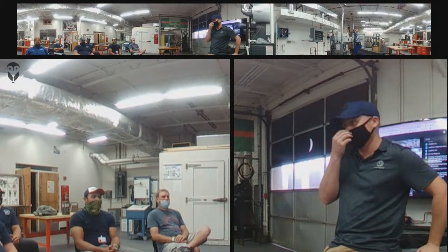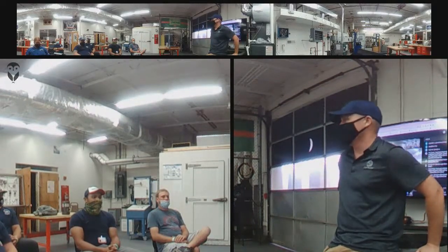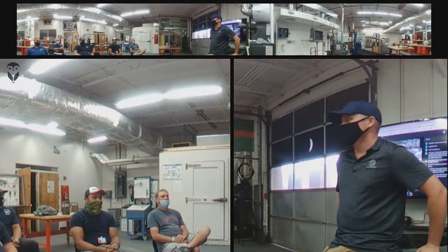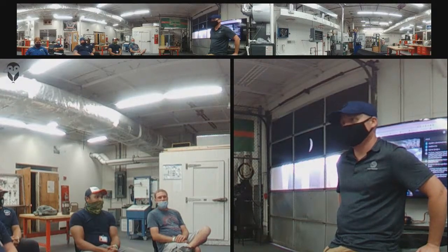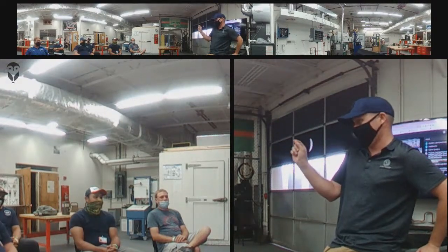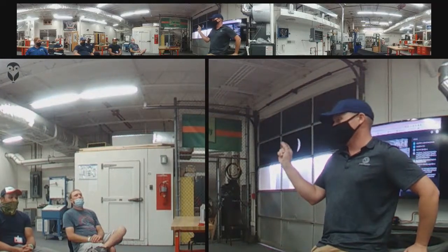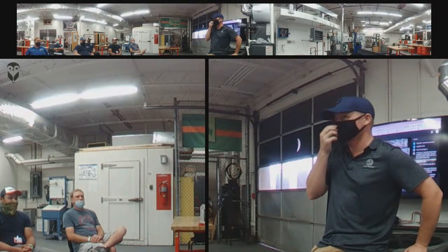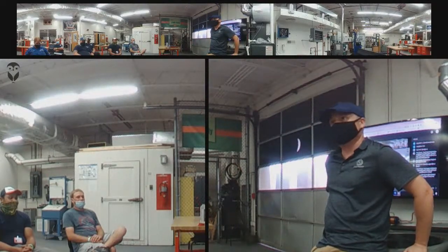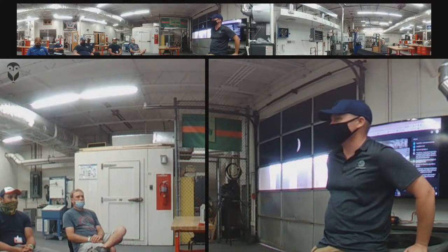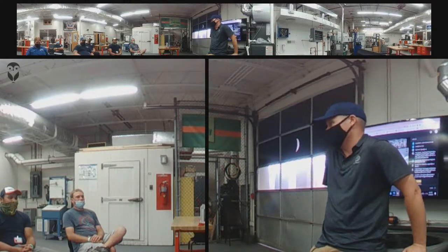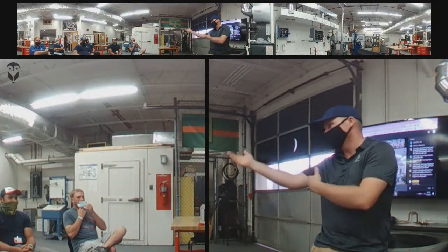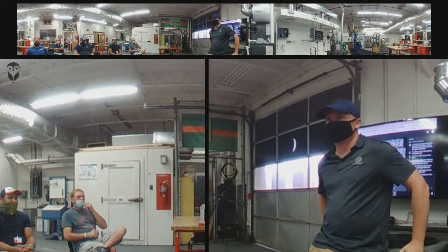Because in a grocery, you've got 2 hours. Otherwise, you start losing frozen product, and it gets really expensive really quick. So, 2 hour time frame, huh? Yeah, 2 hours. And it's 2 hours from the time that you get the call, not 2 hours from the time you show up. It's 2 hours from the time the rack goes down before you start losing frozen foods. Yeah, no bueno. And that's where refrigerated trucks come in, because in some cases you have to unload. When you've got a whole rack down, you've got nowhere else to put it. If you've got a case down, then you can put it into your walk-ins or something else.